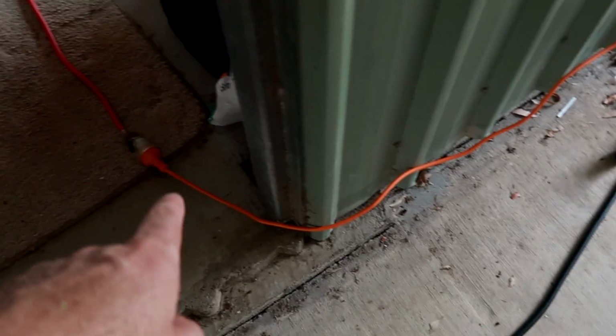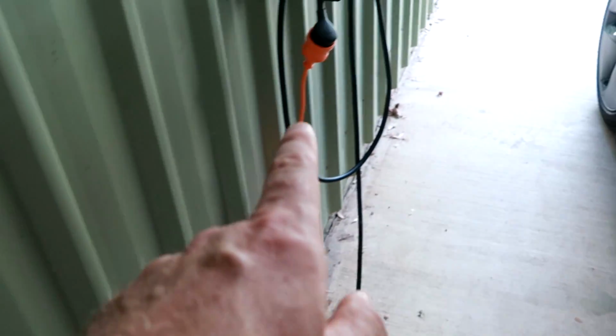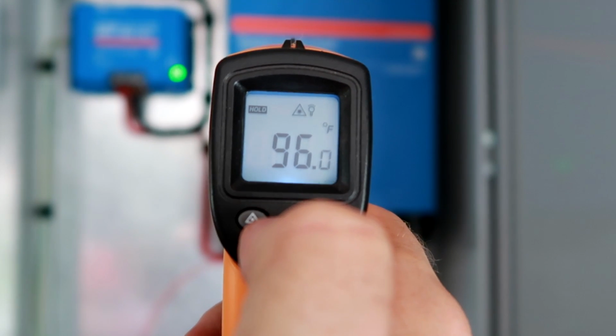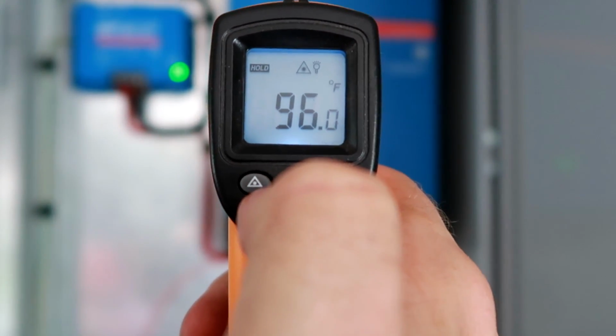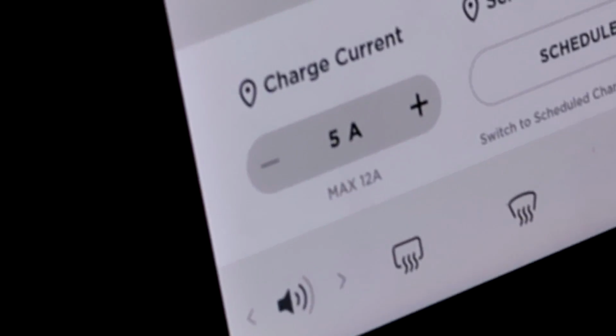I have to use this adapter, unfortunately, again from 10 amps to 15 amps. With a 10 amp circuit breaker and RCD, that way around. Otherwise we cannot utilize the full 12 amps inside the car, which I would like to test now and see if the inverter can cope with that and what temperature it gets. So after our shredder and mulching activity this morning, the inverter was just idling for about an hour, which is 96 Fahrenheit. Okay, we will start with 5 amps only.